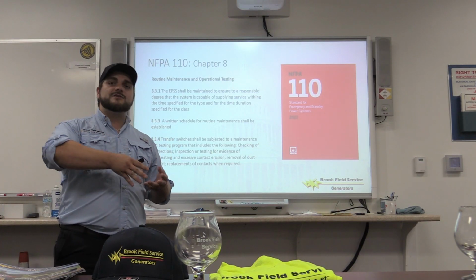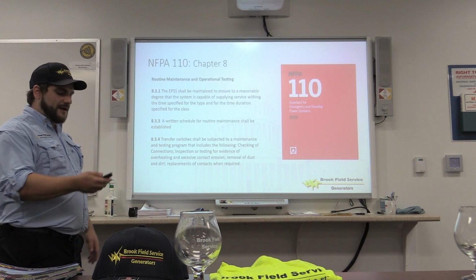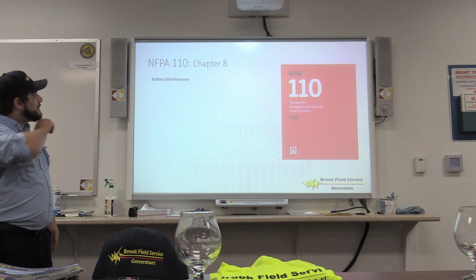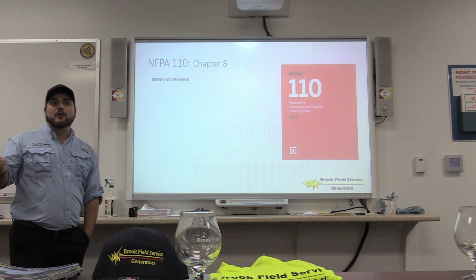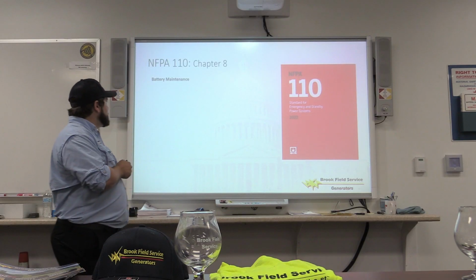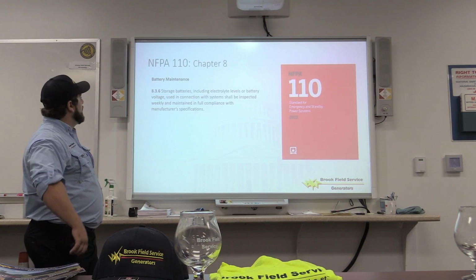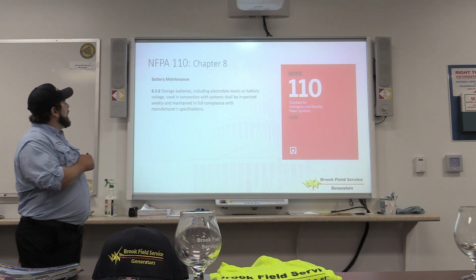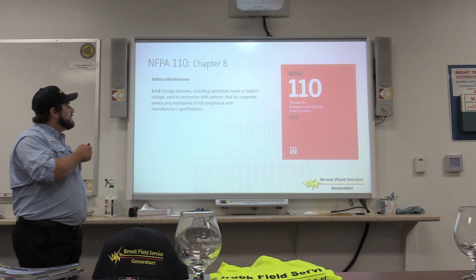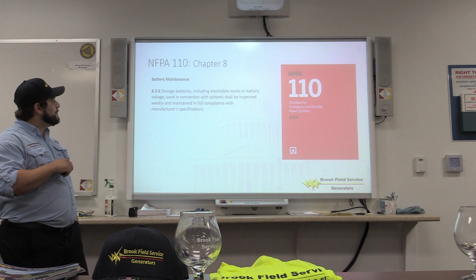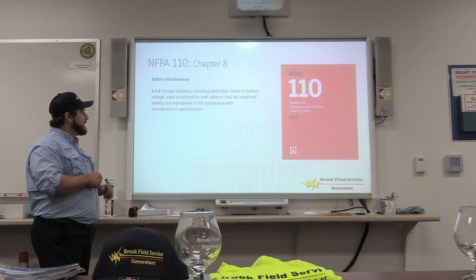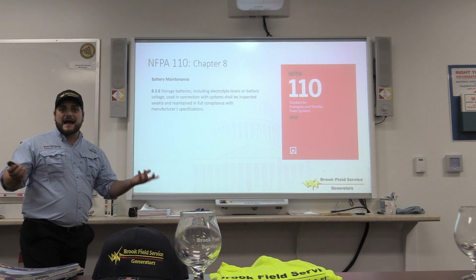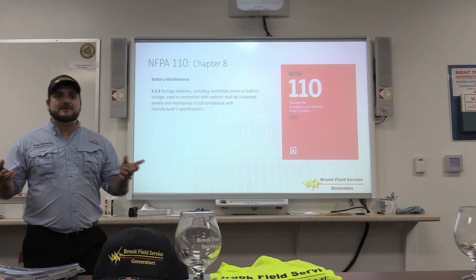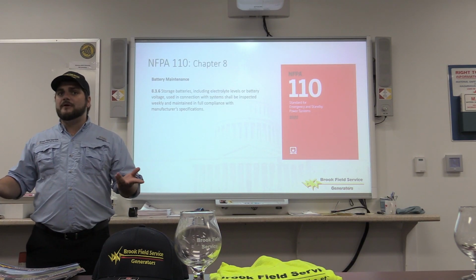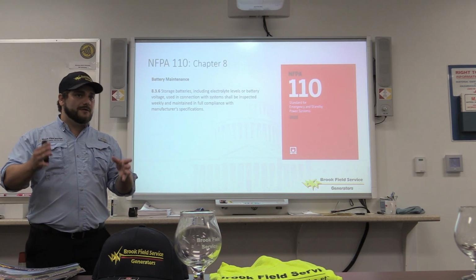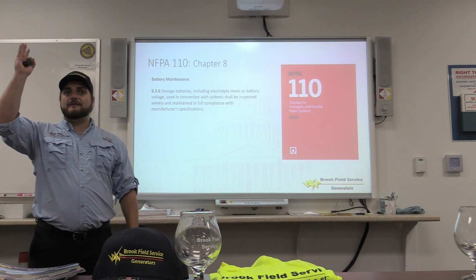We service the transfer switch as well as the generator, so you don't have to deal with any of the extra scheduling. Battery maintenance is, again, we'll talk about at the end, one of the most important things that gets completely overlooked in the generator systems, that fails when you have an issue. Storage batteries, including electrolyte levels of battery voltage, used in connection with systems, will be inspected weekly and maintained in full compliance with manufacturer's specifications. I'm sure you guys have the voltage reader on the controls, but I will talk about in a minute investing in a multimeter, just to make sure that you have the ability to have the analog test instead of relying on a faulty control.